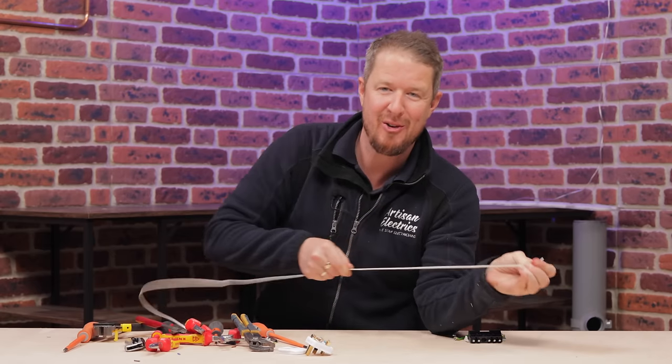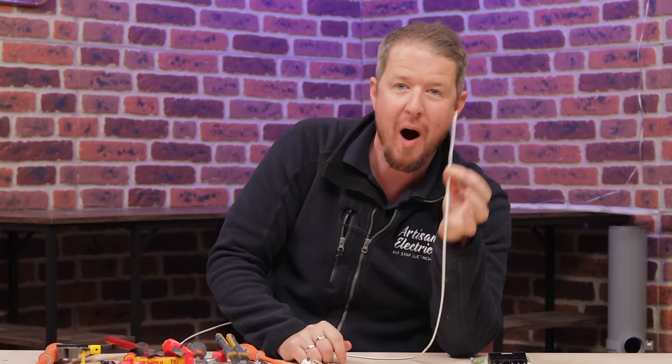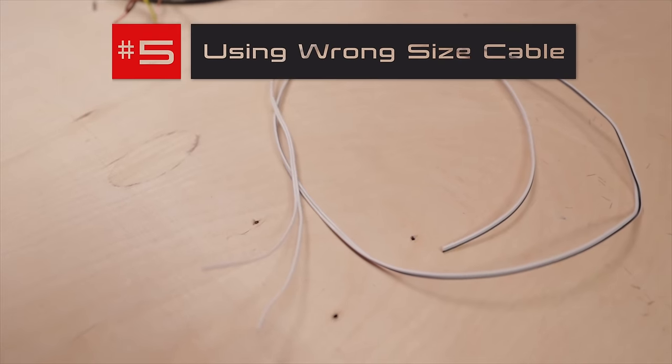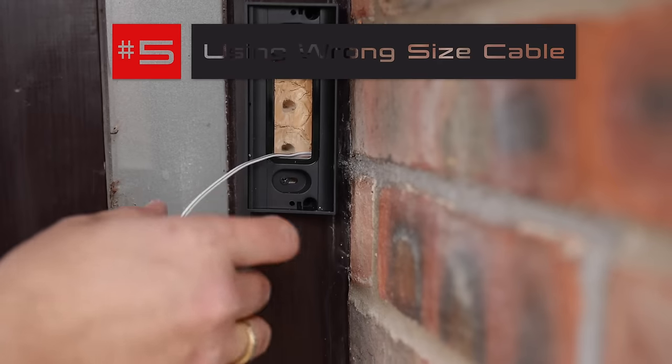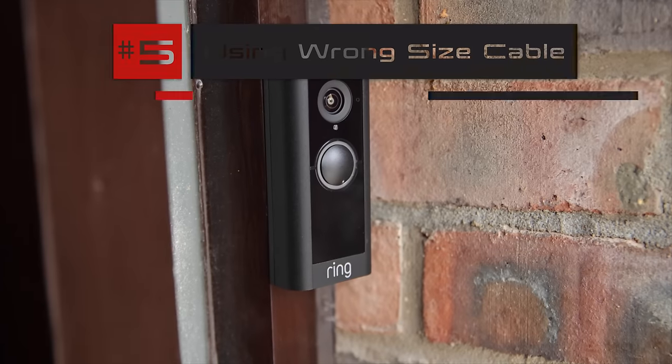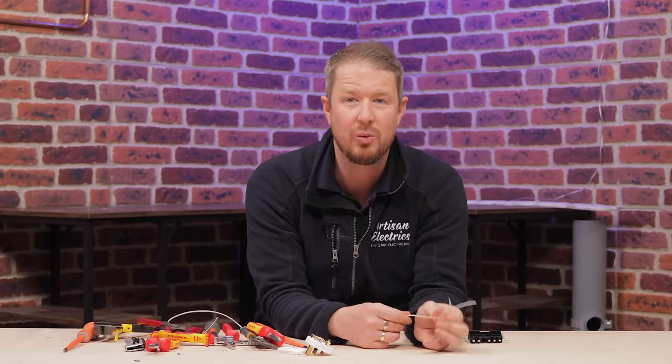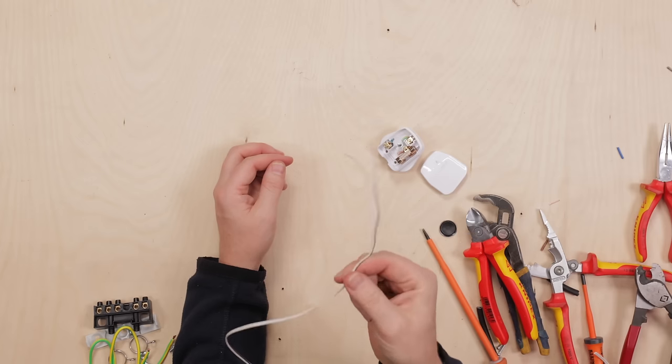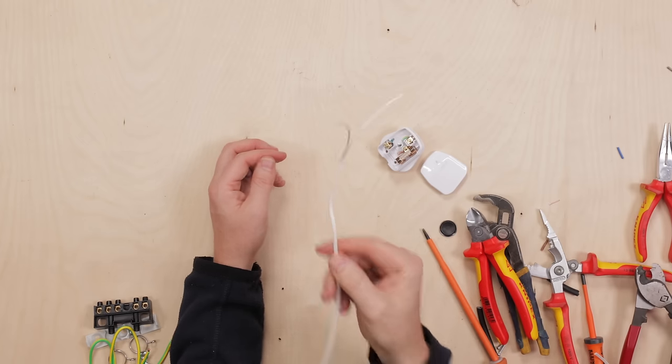Another DIY classic that we see a lot is using the wrong size cable. For example, this is one of the worst ones. Wiring lights in bell wire. Now bell wire is designed for exactly what it says. Wiring up doorbells. It's not designed for any kind of heavy power or voltage. It's just designed for like 12 or 24 volt signals for doorbells. But the amount of times I've seen people wiring up their shed or their loft lights with bell wire is beyond belief.